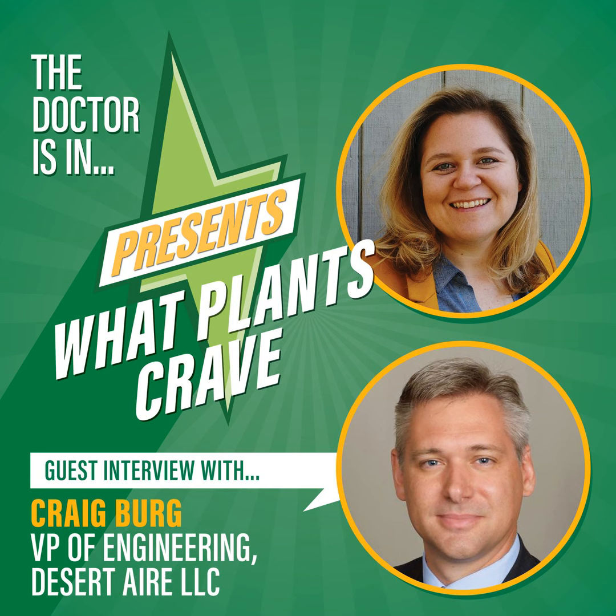There's an advantage to packaged systems. When it comes to reliability, isn't it nice to go to the manufacturer and say, I'd like a package from you, set it on the rooftop, and avoid a lot of the piping from here to there, dealing with big questions about oil and refrigerant management. Growers may not realize this, but running a pipe a couple hundred yards can be very difficult. That line carries oil and refrigerant, and pressure drop and velocity both matter. So these systems that essentially become field-built can have a downside, as well as an upside, to doing that.